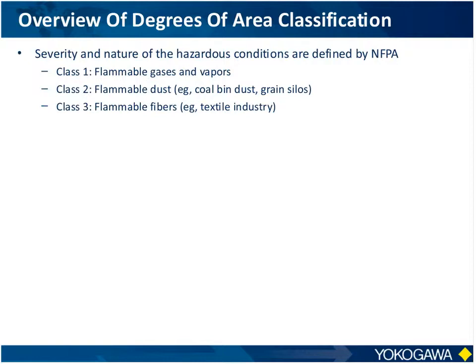For example, in the chemical industry and refineries, it's typically some type of hydrocarbon gas or vapor—that's Class 1. Growing up as a kid in the Dakotas, we had wheat grain silos, and every now and then you'd hear about one exploding because you can get explosive flammable dust from coal bins or grain silos—that's Class 2. Finally, Class 3 would be like in the textile or carpet industry, where very fine fibers from textile mills can create a potentially explosive environment.